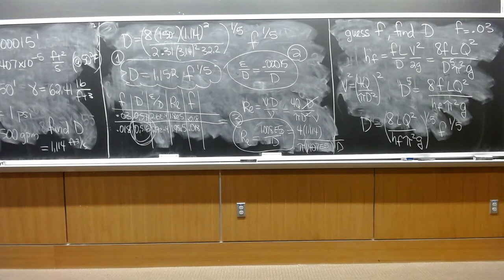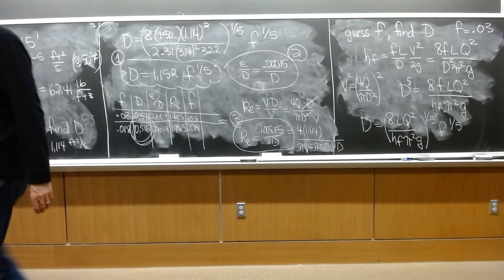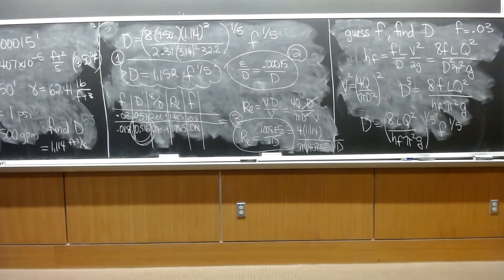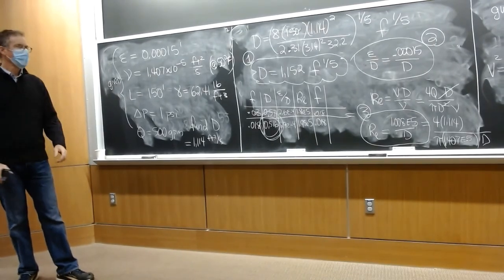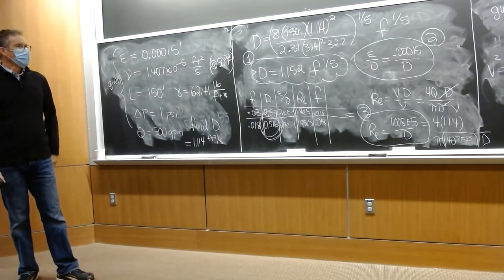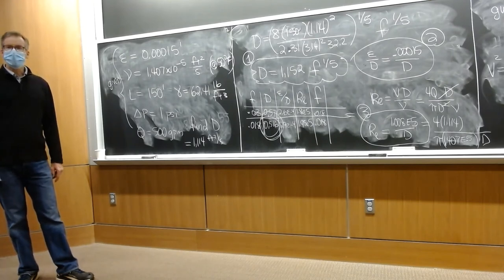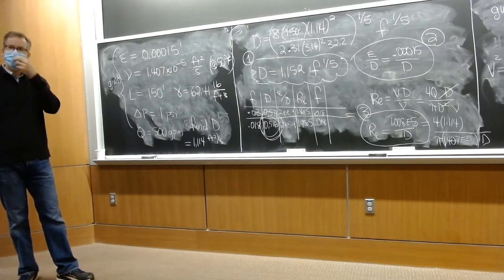Yeah, well, they actually calculated that it'd be a 6.37-inch pipe, and they did it in a different fashion. They actually guessed at the pipe diameter and then calculated the pressure drop. They guessed this size pipe, guessed the next size pipe, guessed the next size pipe, and looked to see what the pressure drop would be in each instance. That's just a different way. That's a guess and check kind of method instead of an iterative method like we've done here. Both work.